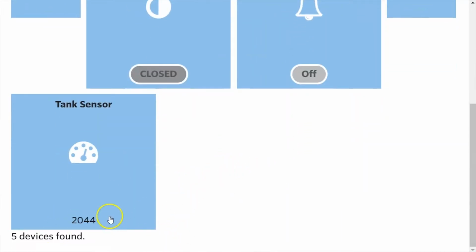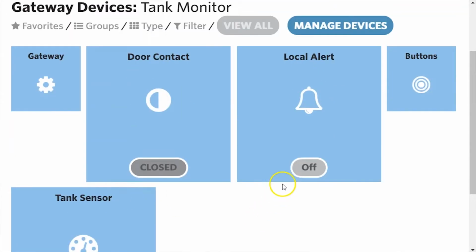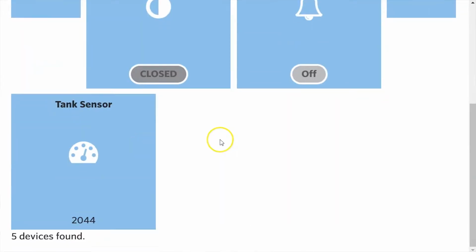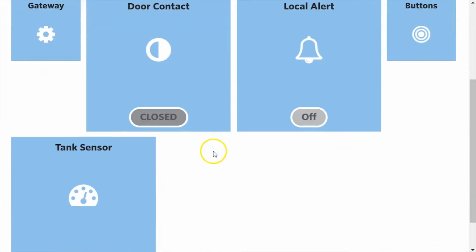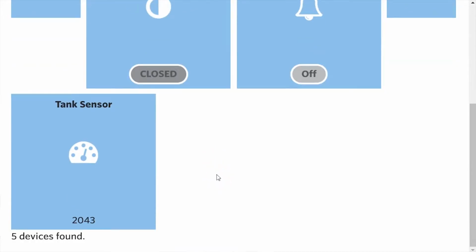Now the tank sensor level is a number that is between 0 and a very large number based on the sensor we're using, the Fortress sensor. We really want to convert that to a number between 0 and 100%, and tank being 0 to 100% full. So to do that, I'll use some coding, and this user interface allows the coding to be inserted right within the scripts itself. So to do this, I'm going to create a new virtual value that's actually going to represent the value, the tank level between 0 and 100%. The sensor is 0 to multiple thousands, but the tank level we want between 0 and 100.